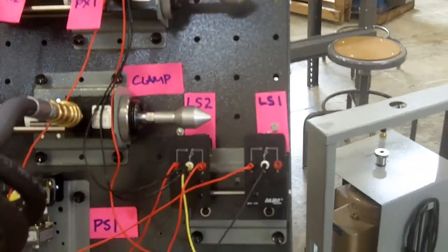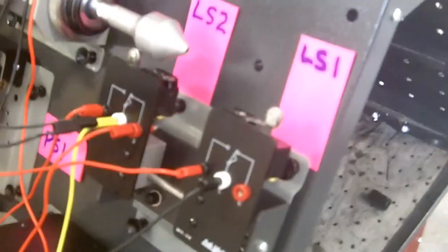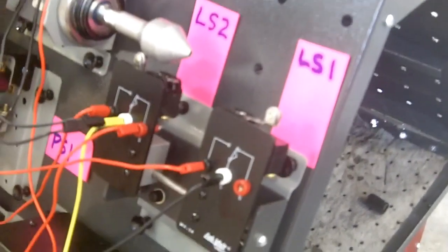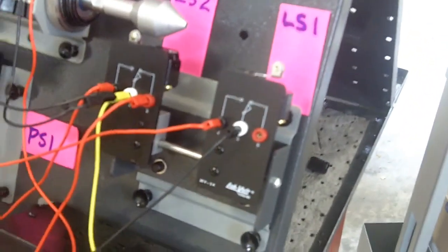That is a purposely introduced error that may represent a limit switch being improperly placed or perhaps the rocker arm of the limit switch being broken off. The limit switch is still functional, but it is incapable of sensing its environment.